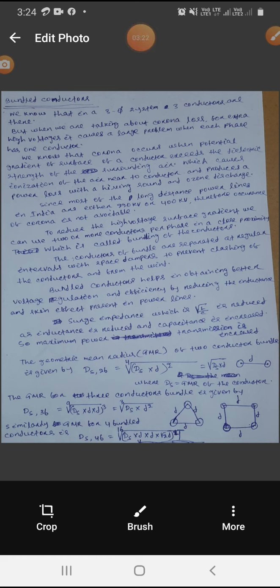When we are making bundled conductors for each and every phase, obviously the inductance is reduced and the capacitance is increased, and because of that the surge impedance of the transmission line is reduced, which is root over of L by C. As L is reduced and C is increased, the surge impedance will be reduced, and when the surge impedance is reduced, what will happen? Maximum power will be transmitted. That means the maximum power transmission of the transmission line is increased when the surge impedance is reduced due to the bundling of the conductors.